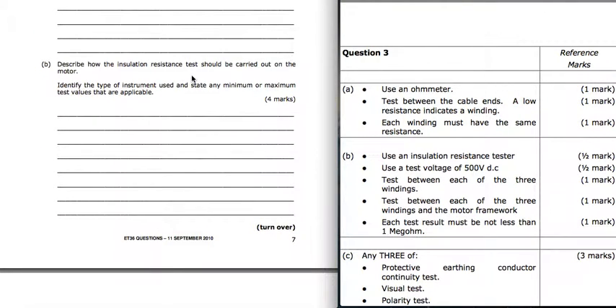We're going to do an insulation resistance test. So type of instrument, insulation resistance tester, don't say mega. Minimum or maximum test values that are appropriate. So we're going to use a test voltage of 500 volts DC. Always put the DC in there. We're going to test between each of the three windings. So you're going to go between winding 1 and winding 2 and make sure that they're not connected. Make sure there's a good insulation resistance between them. And then 2, 3, 3, 1. So between each of the three windings. And then you're going to test between each of the three windings and the motor framework earth to make sure none of those windings are touching earth. Each test result must not be less than 1 mega ohm. So there's our 1 mega ohm for insulation resistance.